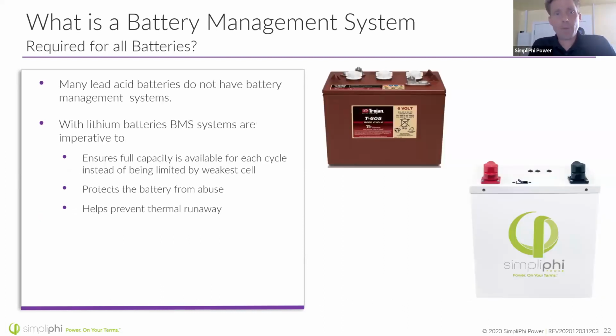Lead acid batteries are very simple batteries. Lead acid batteries typically do not have a battery management system. They do have an electrolyte, and that electrolyte is sulfuric acid. And that with lead acid batteries was typically very, very problematic, right? The water would evaporate, resulting in a much more concentrated acid, and you would have to water these batteries. The nice thing about lithium batteries is they don't need servicing, right? They don't need monitoring of electrolyte. Pretty much once you install this battery and get it programmed properly, it will be easy to use and maintenance free, but it does have a built-in BMS.